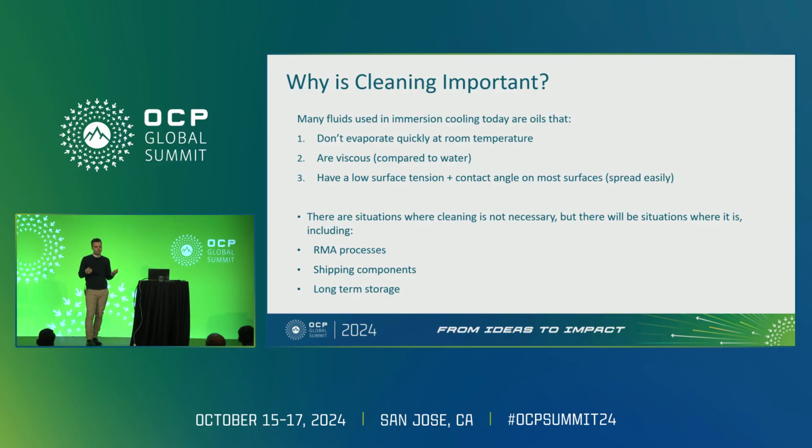Many of the fluids we use today in immersion cooling, especially in single-phase immersion cooling, are oils, essentially, right? And they have these properties. They don't evaporate quickly at room temperature. They're quite viscous compared to a fluid like water. And they have a low surface tension and contact angle, which means that they spread really easily on the surfaces of the IT equipment.